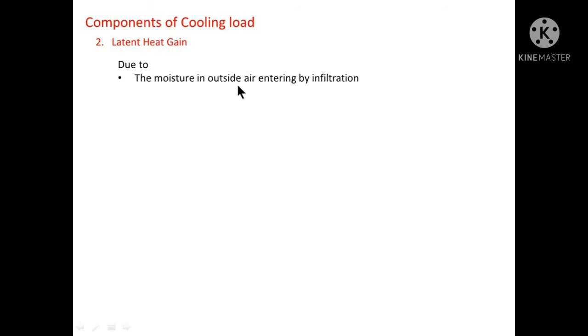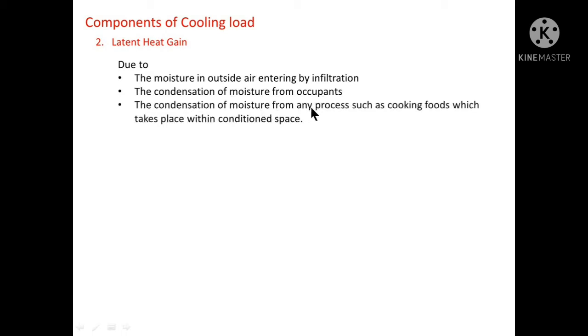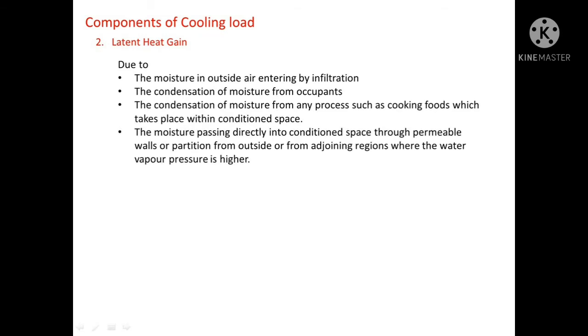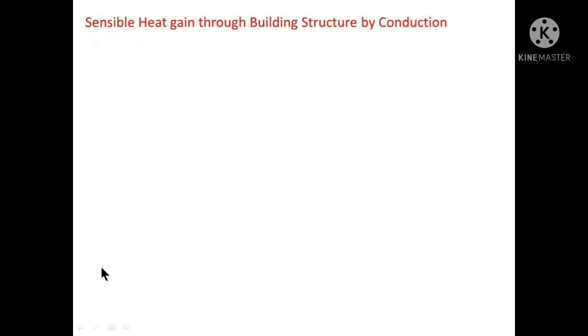The latent heat gain category includes moisture in outside air entering by infiltration, condensation of moisture from occupants, condensation of moisture from any process such as cooking foods taking place within the conditioned space, and moisture passing directly into the conditioned space through permeable walls or partitions from outside or from adjoining regions where the water vapor pressure is higher.